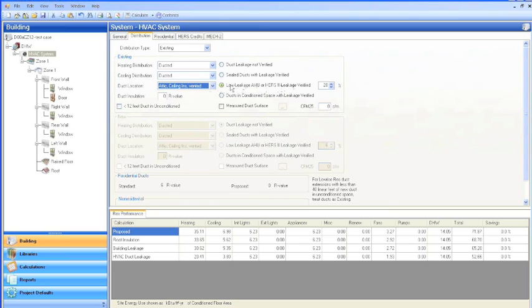Make sure you click on this button right here so you can enter in the tested duct leakage level. And then go to the residential tab. Make sure this says setback. That's true for all jobs. Just as a standard for the program, it's presumed that there is some adjustment of the thermostat between winter and summer, and so that there is a usage of setback there.